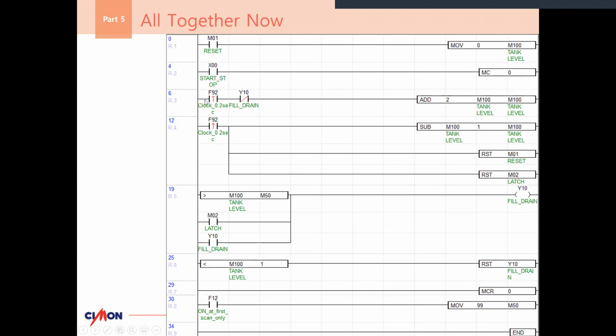On the next row, we see some F92 bits. These are internal clocks. As a reminder, F is read-only. F92 is on for 0.1 seconds and off for 0.1 seconds, and these are also one shots. So Y10 is off by itself by default.